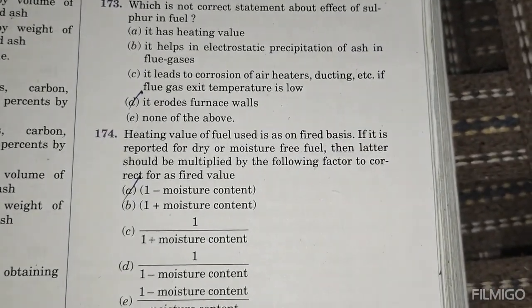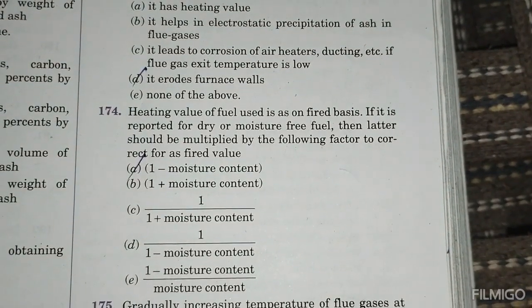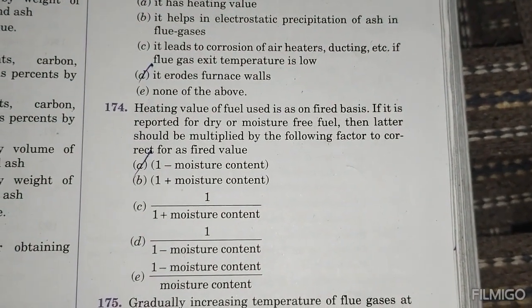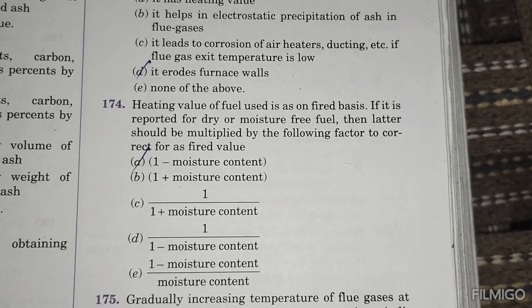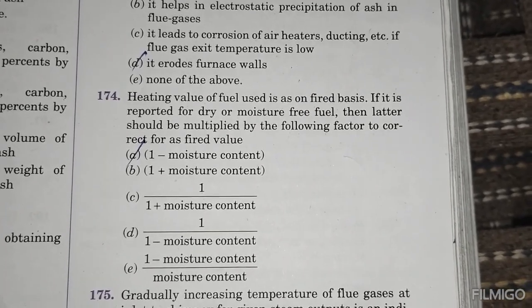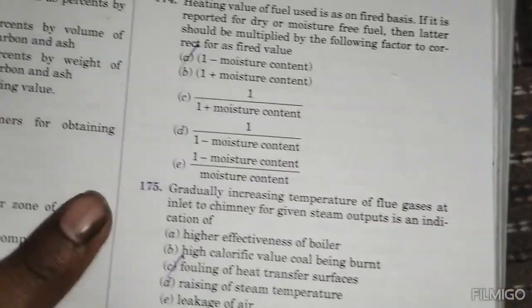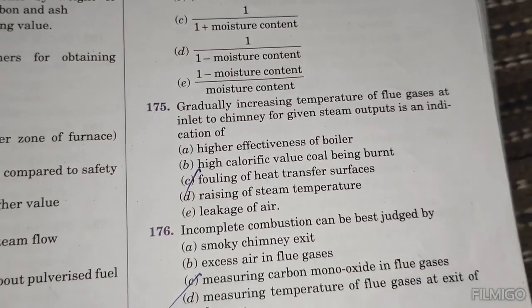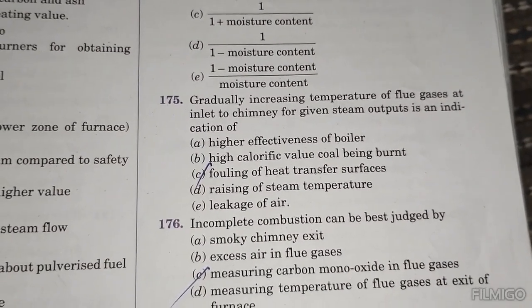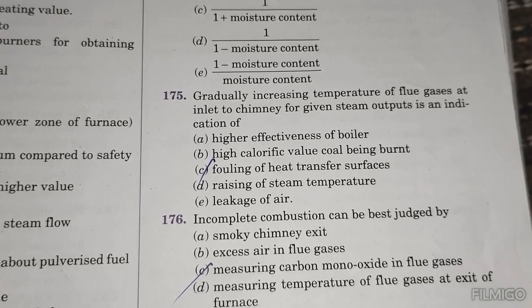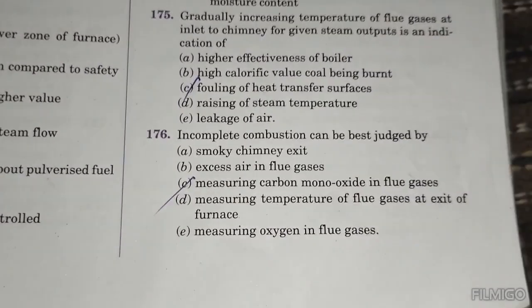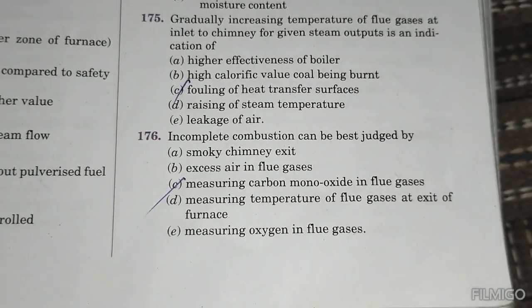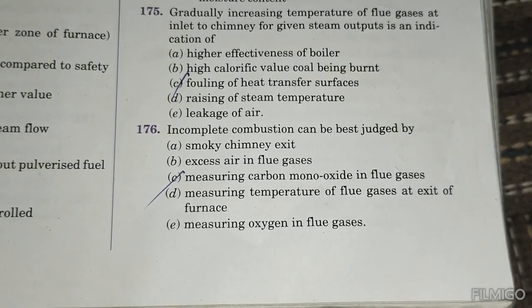Heating value of a fuel is reported on an as-fired basis. If it is reported for dry or moisture free fuel, the latter should be multiplied by the following factor: 1 minus moisture content. A gradually increasing temperature of flue gases at the chimney inlet for a given steam output is an indication of fouling of the heat transfer surface. Incomplete combustion can be judged by measuring carbon monoxide in the flue gases.